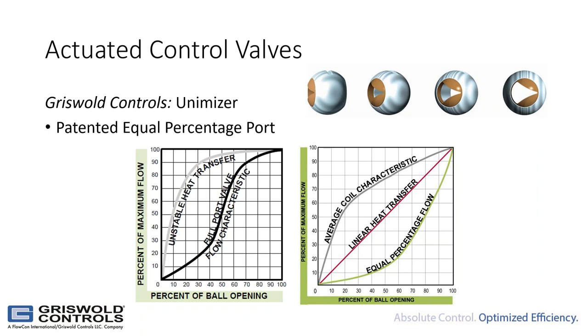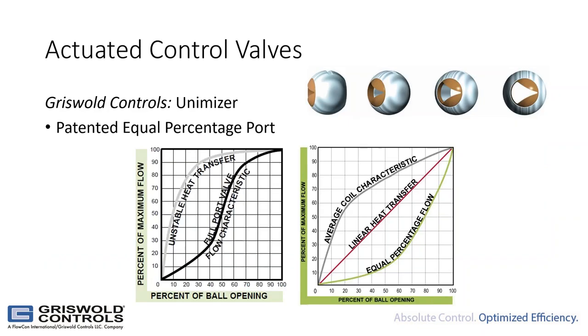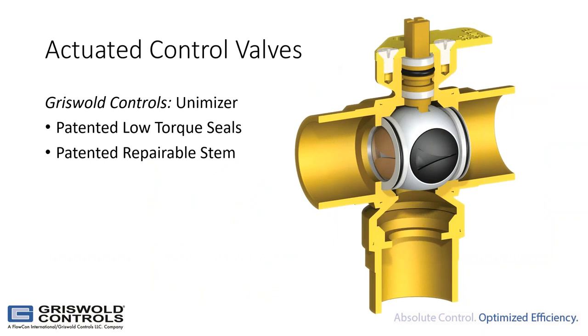Ball valves were a fairly low-cost way to do control valves, but the problem was they were not equal percent. By designing the ball valve with our patented optimizer insert inside, we solved one of the main downsides of actuated ball valves in the industry. The optimizer is in all of our Unimizer products, the PICV, and the Automizer. The second benefit of the optimizer is it brings the CV value down — a full-port ball valve is about 11 CV in three-quarter inch size, far more than most applications need.